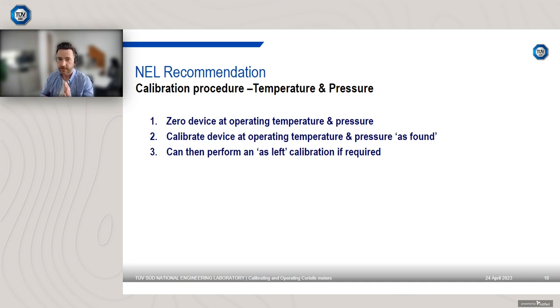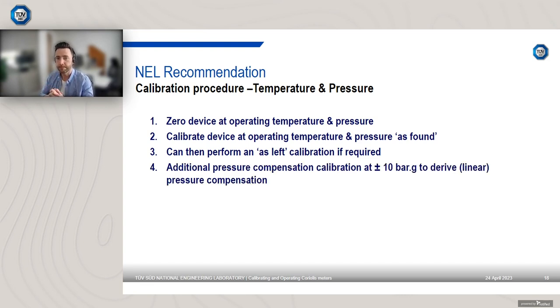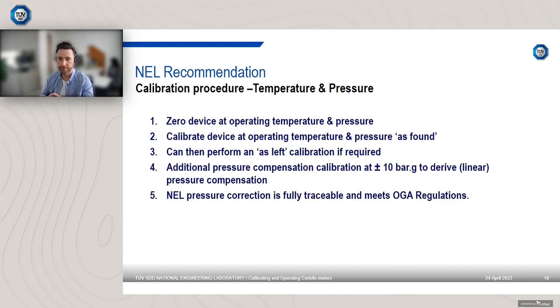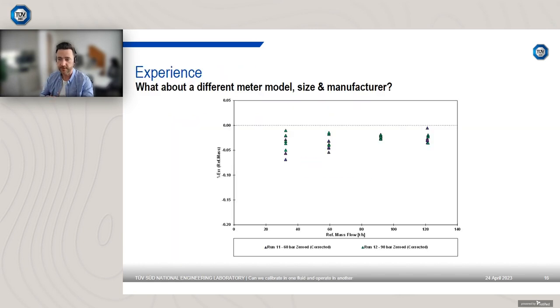So this is what we recommend, and I'll discuss what we recommend for pressure in a second. So we recommend that you zero the device at operating temperature and pressure. You then calibrate the device at operating temperature and pressure as found, so no adjustment yet. You can then perform that as left calibration, so you can adjust the mass factor if you have to. You then want to conduct additional pressure compensation calibration at plus or minus 10 bar to derive the linear pressure compensation factor. Apologies, go back to that previous slide there.